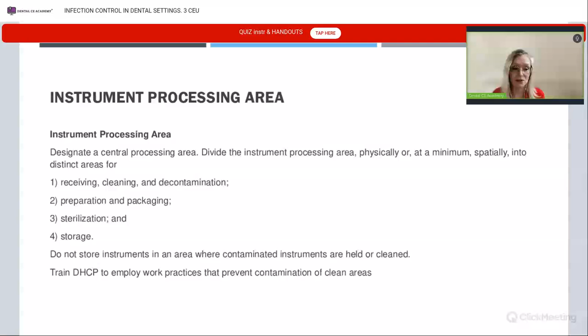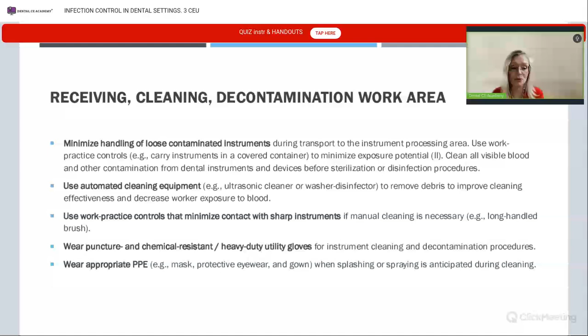All right, your instrument processing area should be divided spatially between receiving, cleaning, decontamination, preparation, packaging, sterilization, and storage. We minimize handling of loose contaminated instruments. We use automated cleaning equipment first, make sure that all the debris is removed from your instruments, and use work practice controls that minimize contact with sharp instruments, wear puncture and chemical resistant heavy-duty utility gloves, and wear appropriate PPE. And most of the time, those heavy-duty gloves now are autoclavable.